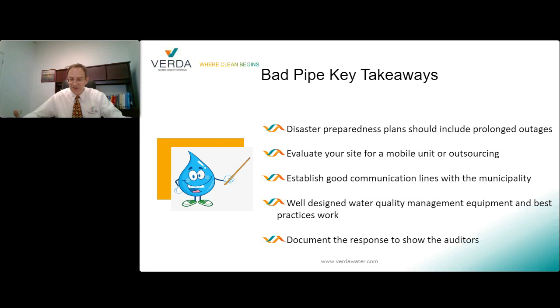Two, maintain good communication with the local water authority. Understand their work can impact your water quality in SPS. The hospital did not initially connect the dots between the work taking place outside the hospital and the defects they were seeing on the processed medical instruments. Know that the work taking place on the water lines that feed the hospital impacts the hospital, impacts you. And local municipalities can and will change their water treatments. They sometimes shock the system with disinfectants. They sometimes flush out the systems, resulting in downstream silt and contaminants entering the hospital piping.